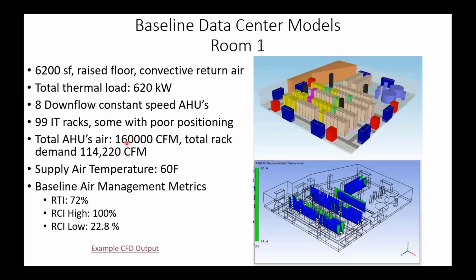You see that ratio right there is off. The racks want 114, we're delivering 160. So we've got too much air coming through the air handlers compared to what the racks want. This tends to make the return air temperatures too cold, hurts the heat exchangers, hurts the chillers, drives efficiency down. Air supply temp, 60 degrees, often I see that, it's too cold. So therefore my RTI is below 100. You can see RCI high is fine. RCI low is 22, it's too cold.